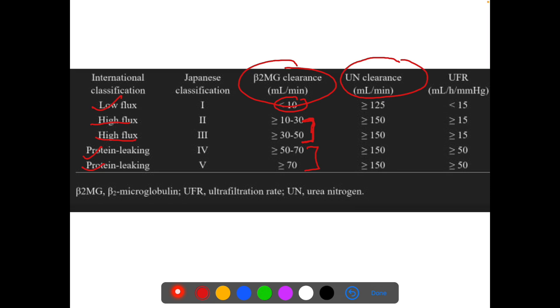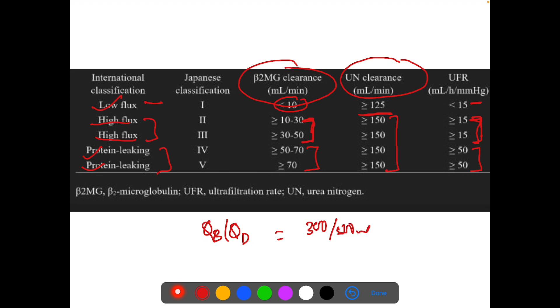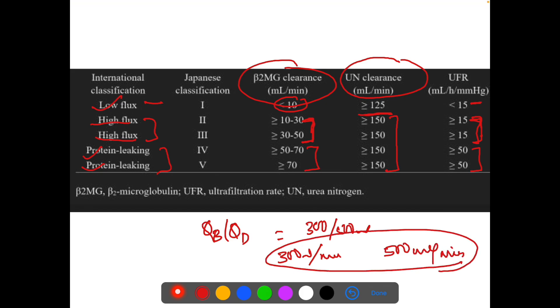The urea nitrogen clearance is also relevant: in low flux it is 125 ml per minute, and in high flux to protein leaking it is more than 150. The ultrafiltration rate is generally less than 15 in low flux, and greater than 15 in high flux and protein leaking membranes. These values are measured when blood flow is 300 ml per minute and dialysate flow in the counter-current direction is 500 ml per minute.